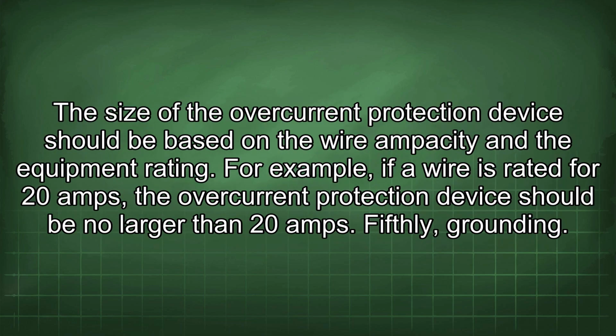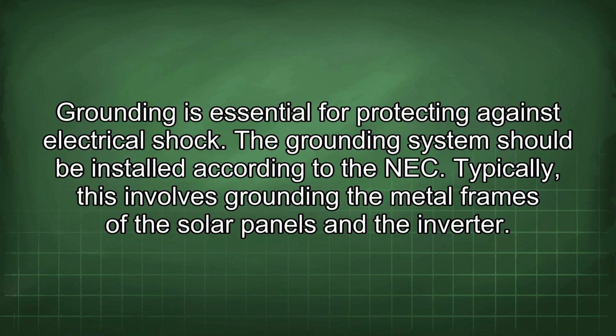The size of the overcurrent protection device should be based on the wire ampacity and the equipment rating. For example, if a wire is rated for 20 amps, the overcurrent protection device should be no larger than 20 amps. Fifthly, grounding. Grounding is essential for protecting against electrical shock. The grounding system should be installed according to the NEC.